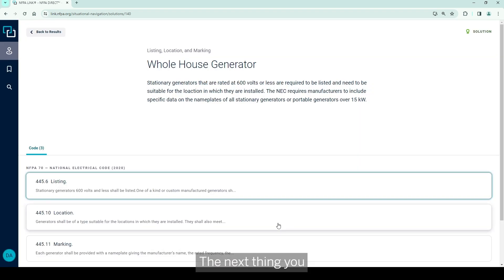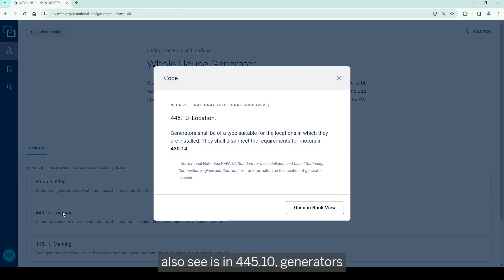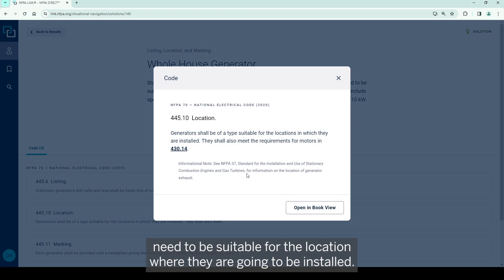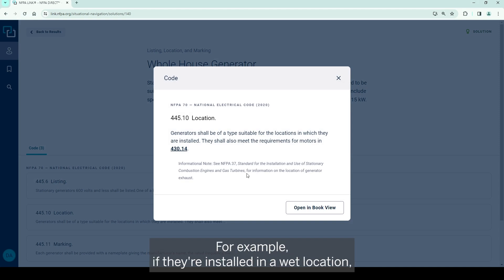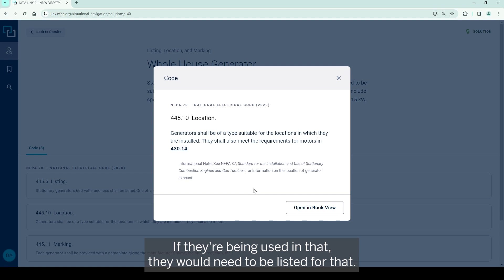The next thing you will also see is in 445.10 - generators need to be suitable for the location where they are going to be installed. For example, if they're installed in a wet location they have to be rated for that, or even more so a hazardous location if they're being used in that, they would need to be listed for that.